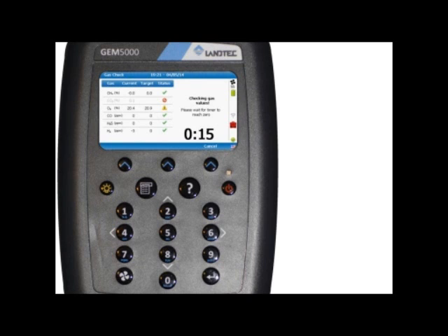So as the timer goes down, you're going to see the symbols going back and forth, the current values getting more stable. When the timer has ended, the message check complete will show up at the top of the screen. The user will have three options on the bottom to select at this point: retry, calibrate, and record. If all channels have a green check mark, you can select record. If you see any channels with the yellow exclamation symbol, we strongly recommend to select calibrate. And if you see any red X's for any channel, you can select the retry option to run the unit longer with gas. In this example, we'll press the middle soft key to select calibrate.